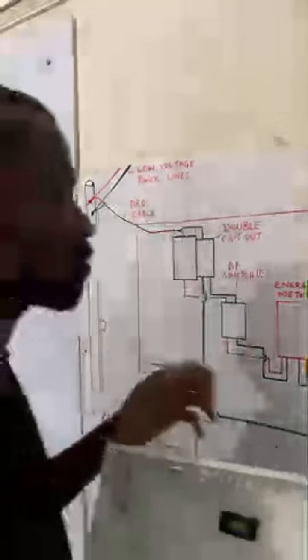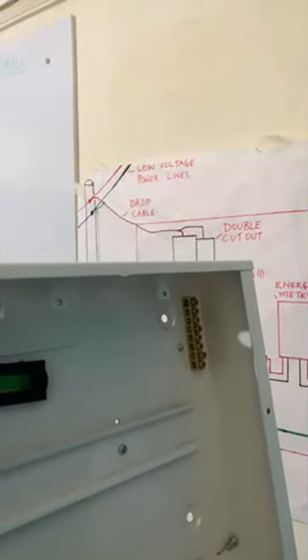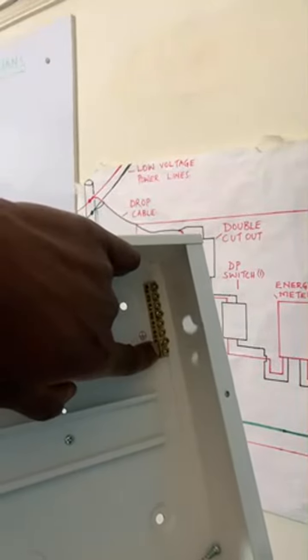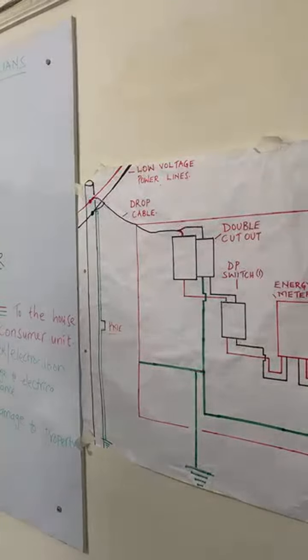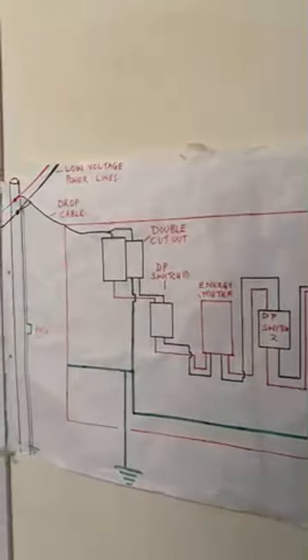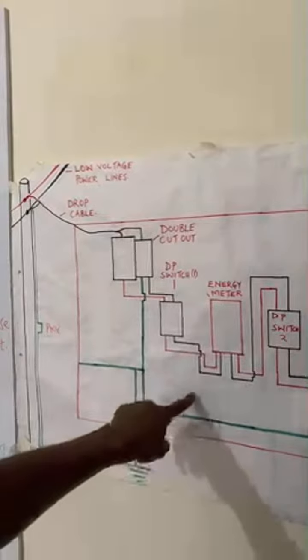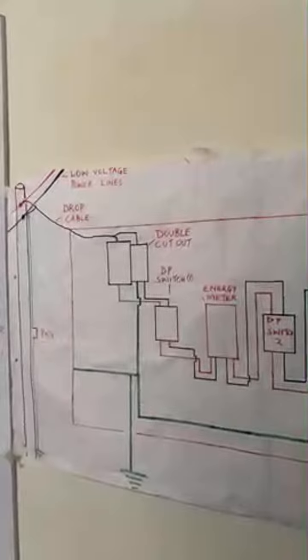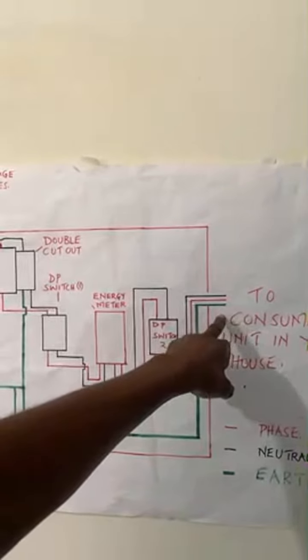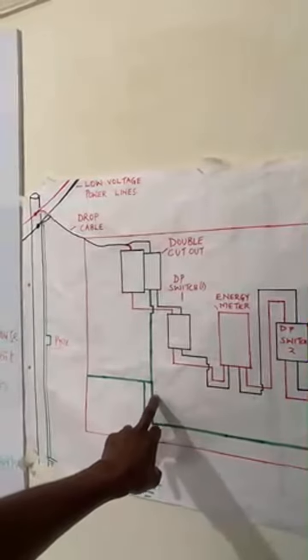Okay, so the charges will flow all the way to the consumer unit, to this bar. First, from the cooker, it will go through the cable to the power socket, and come all the way to the consumer unit, where it will get to this earth bar. This earth bar is now connected to the earth wire, which flows from the consumer unit, as we can see there, to the point I've indicated it should be here, and then it will flow all the way to the earth rod. So you can see this cable. Let me just flow with you. So you can see from the consumer unit, it will flow all the way. This will be the path. It will flow very fast, unnoticed, and then to the ground.